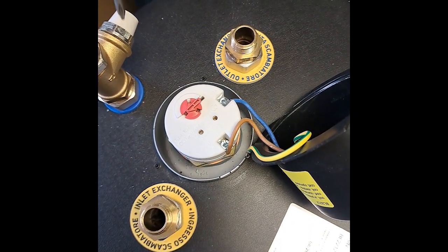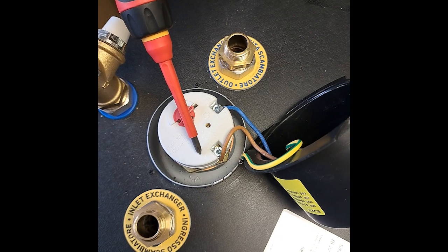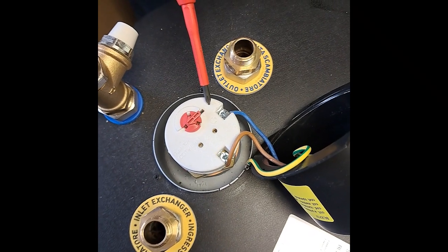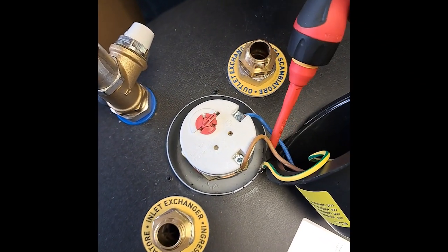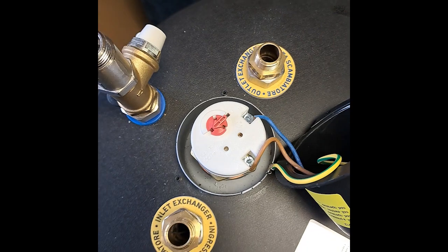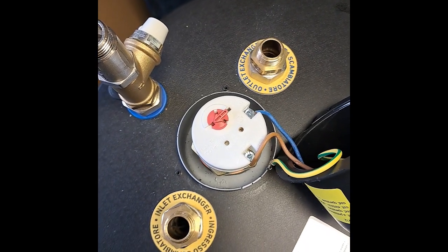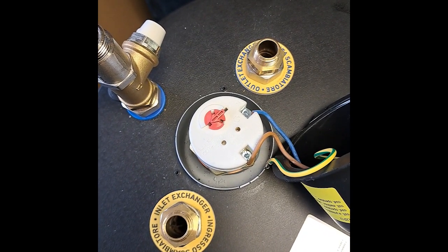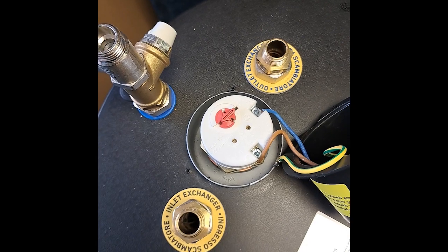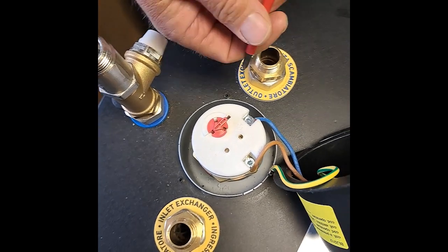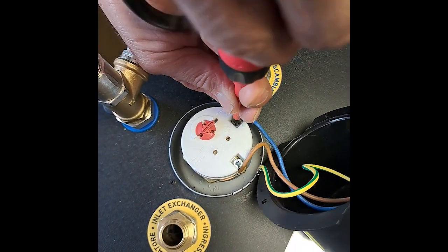The terminals are marked on the top of the thermostat. There is an A for the brown live, B for the blue neutral, and here is where the ground wire is attached to the body of the unit. Now we're going to remove the wiring. You don't need to take the screws all the way out, just undo them enough to allow the ends to slip away.